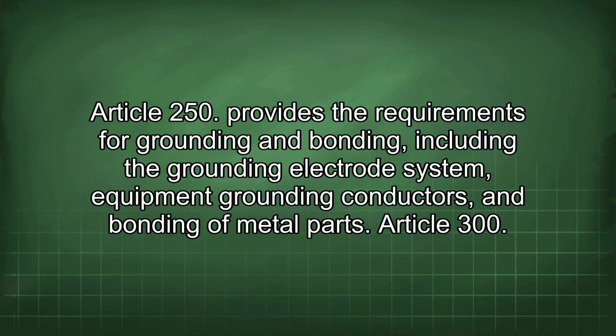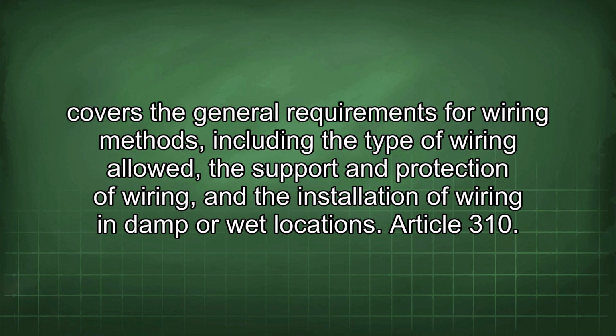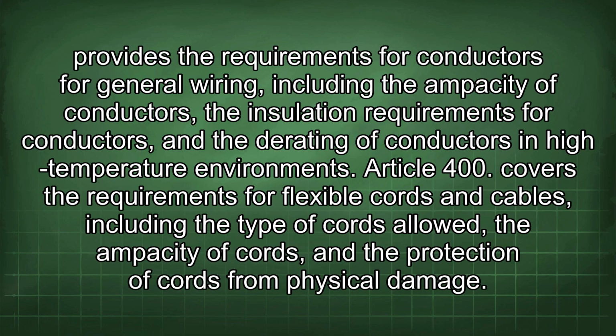Article 250 provides the requirements for grounding and bonding, including the grounding electrode system, equipment grounding conductors, and bonding of metal parts. Article 300 covers the general requirements for wiring methods, including the type of wiring allowed, the support and protection of wiring, and the installation of wiring in damp or wet locations. Article 310 provides the requirements for conductors for general wiring, including the ampacity of conductors, the insulation requirements for conductors, and the derating of conductors in high-temperature environments.